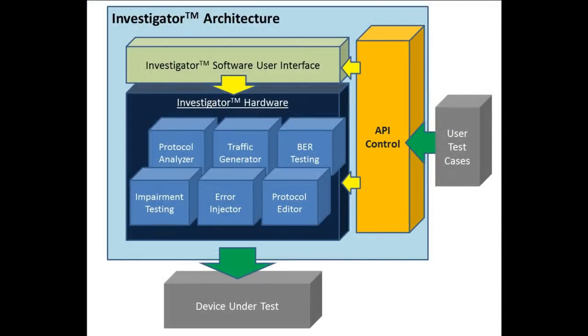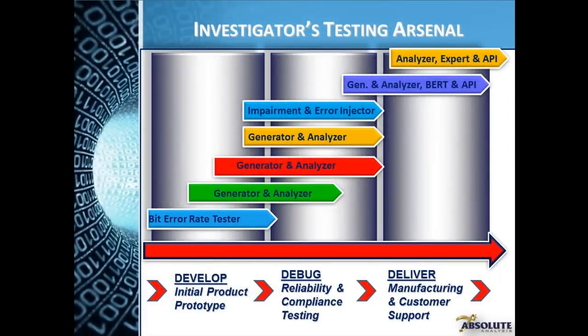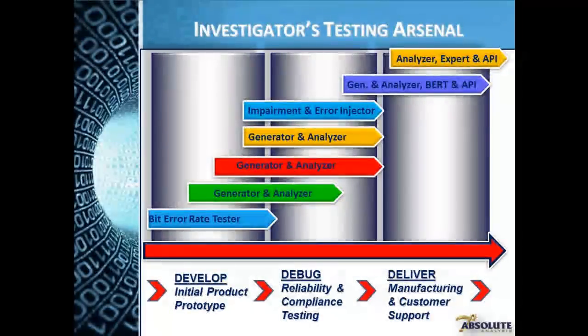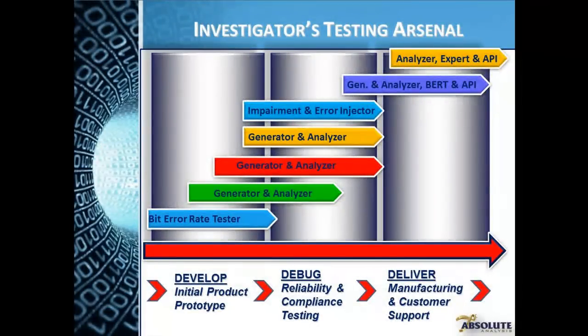Now add in the Investigator API that allows you to control all aspects of the Investigator's operation. This facilitates and supports test automation and consistency. With this, test teams can design their own GUI to operate the system as part of a manufacturing test plan, or to integrate the system into a larger testbed such as LabVIEW.